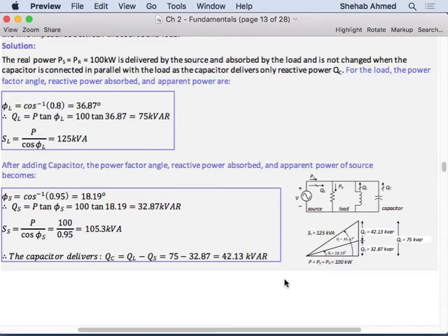Yes? Is it possible to have a lower power factor? Lower? What do you mean lower? Yeah, you can. Yes, 0.7. You go to your home, it's going to be probably 0.7. Because the air conditioners, these split unit air conditioners, they're horrible. They have very poor power factor, actually. Especially the old ones.